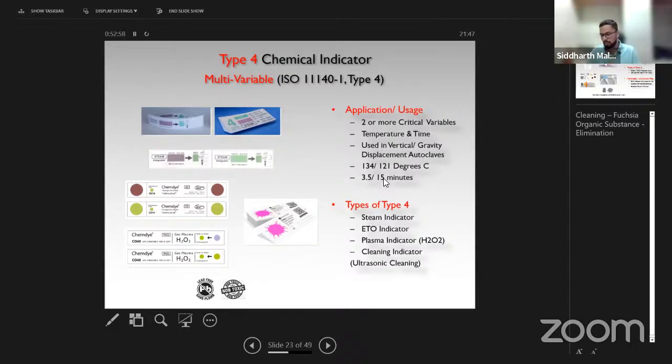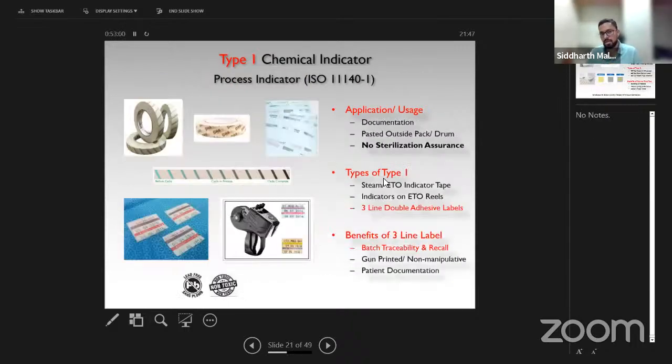Good question, sir. Basically, sterilization remains the same. Either an item is sterile or it is unsterile. There is nothing called partially sterile. Even if you are using a small vertical autoclave, it has to make the thing sterile, irrespective. There can be no partial sterile or full sterile. Now, those vertical autoclaves, I understand, do not have a vacuum pump. That is why it may be difficult to pass a couple of indicators.